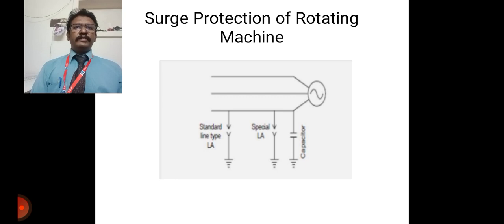The major insulation is normally determined by the expected line to ground voltage across the terminals of the machine, whereas the minor insulation is normally determined by the rate of rise of that particular voltage. Therefore, in order to protect rotating machines against surges or overvoltages, it requires limiting the surge voltage magnitude at the machine, particularly at the terminals, and sloping the wavefront of the incoming surges. This point you have to keep in mind.